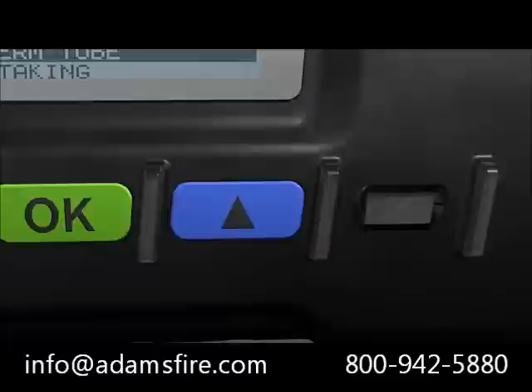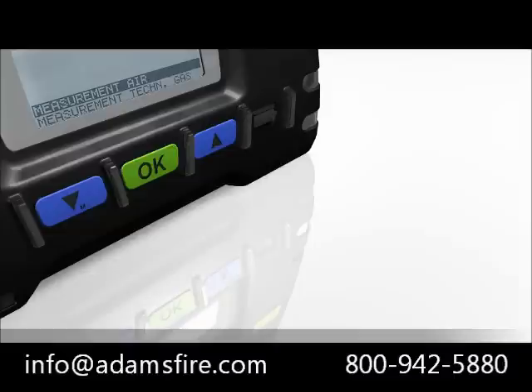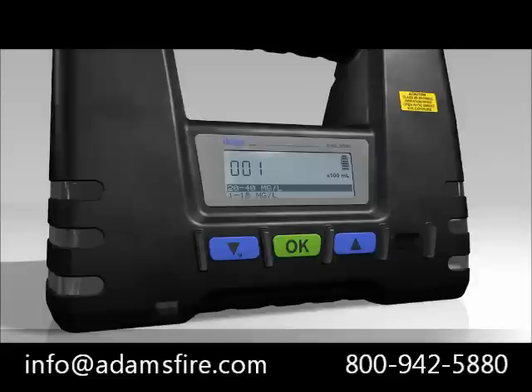On the bottom right is a barcode reader. The invisible laser beam can read barcodes on the back of Dräger short-term tube packaging. When the barcode reader has scanned the barcode, the name of the substance to be measured, the number of strokes, and the appropriate measuring range are automatically shown in the tube pump's display. This simplifies measurement preparation and minimizes possible error.